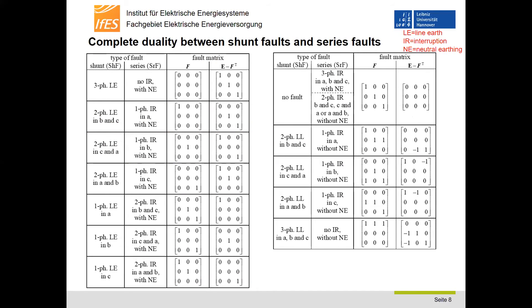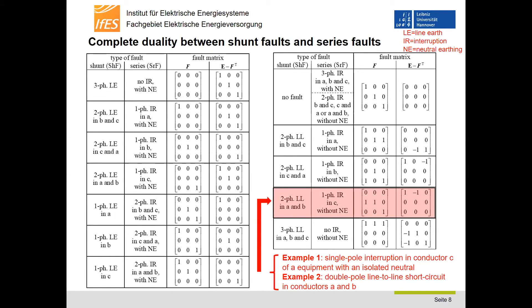A table is presented which shows the complete duality between shunt faults and series faults and the corresponding fault matrices. In particular, the duality between line-to-line short circuits and the corresponding fault matrices is shown on the right-hand side. The first example deals with an ideal single-pole interruption in conductor C of an equipment with isolated neutral, and the second example deals with an ideal double-pole line-to-line short circuit in conductors A and B. Both faults use the same fault matrix, as highlighted in red in the table.